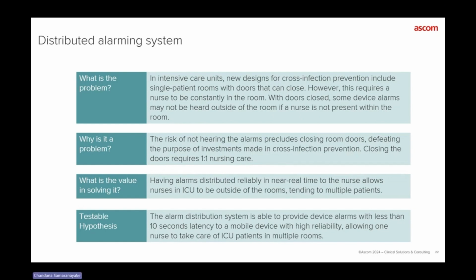The problem is, if bedside devices generate alarm sounds and you close the door, you won't hear those alarms. If you're not receiving them on your mobile device, you'll miss them. So without a system distributing alarms to mobile devices, you defeat the purpose, because you have to keep the door open to hear alarm sounds from the corridor — so a nurse caring for two or three patients can hear alarms from the others. That means the risk of not hearing alarms can lead to patient events, and keeping doors open defeats the purpose of building single patient rooms in the first place.